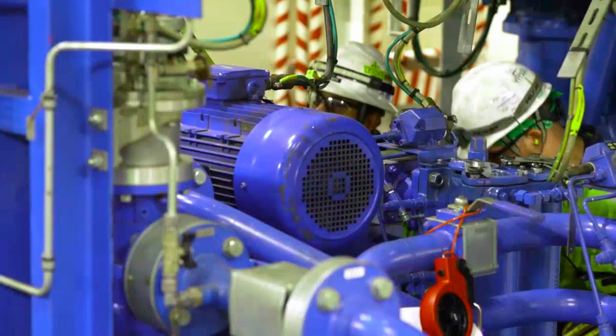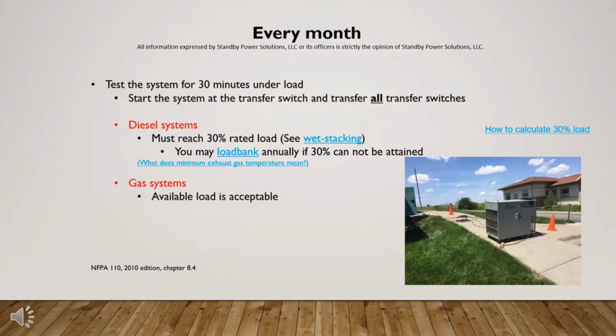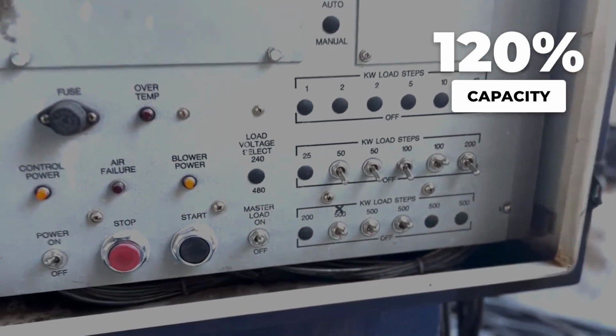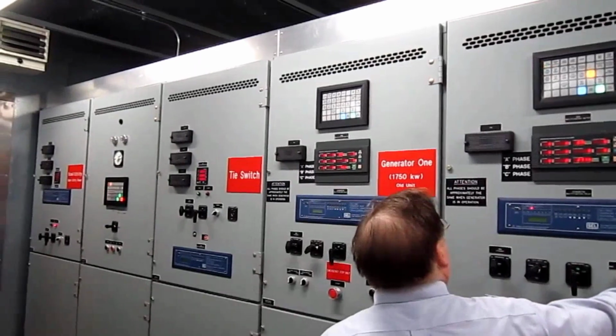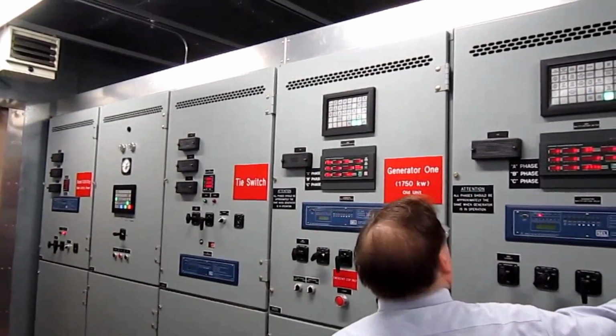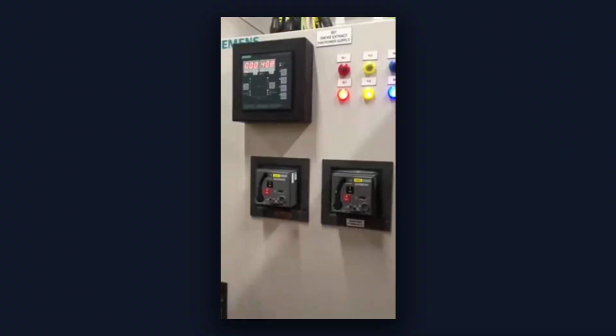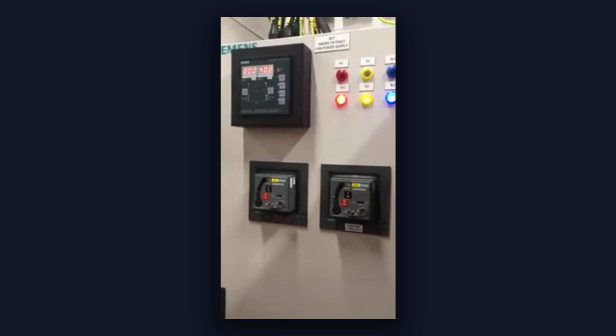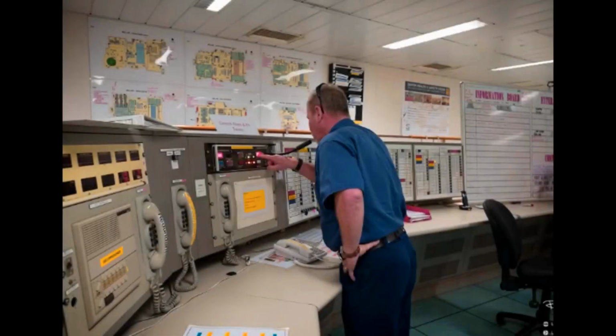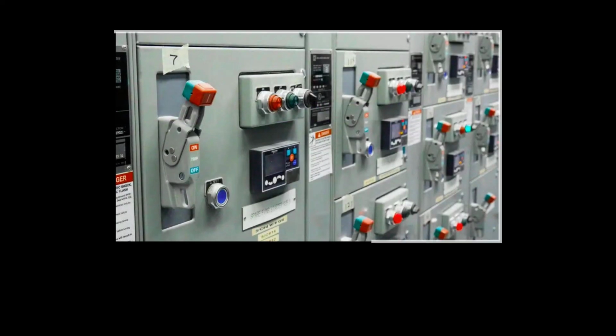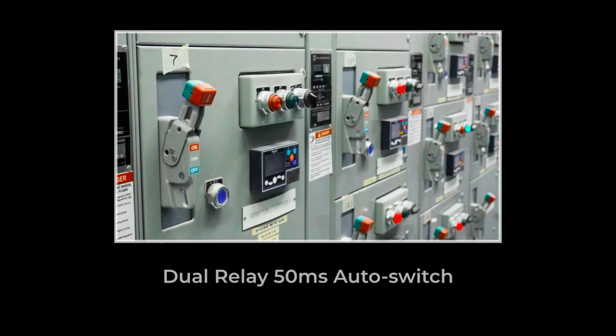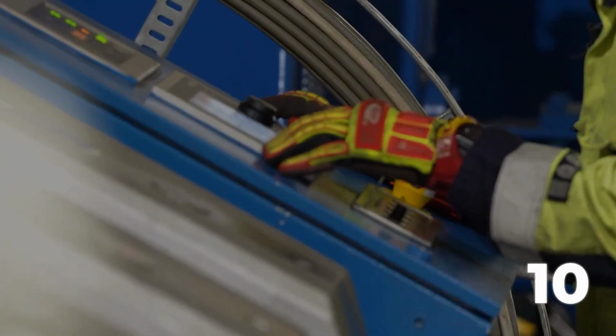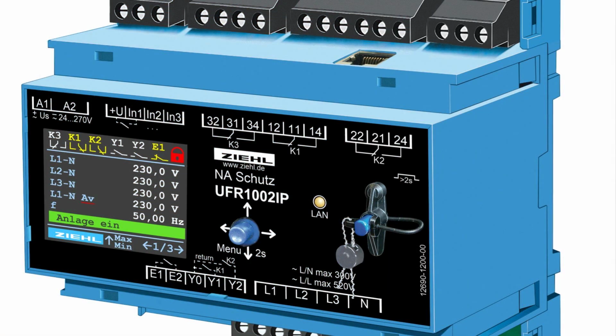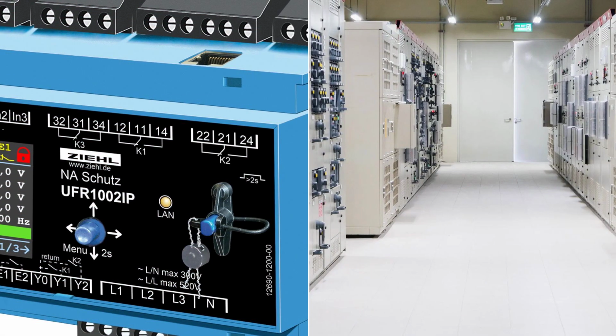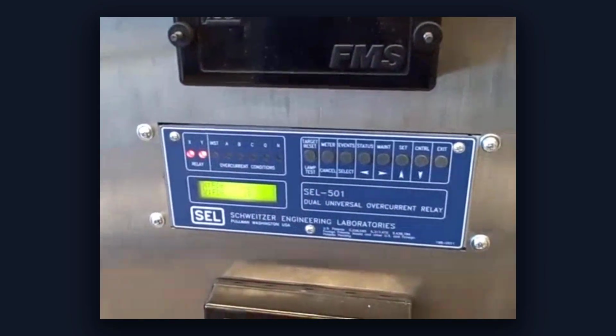The chief electrician begins each shift by checking the status of the primary and standby generators. Each is sized to handle 120% of the platform's peak demand, ensuring that if one fails, the other can carry the full load without hesitation. Automatic transfer switches monitor voltage and frequency around the clock. If the primary generator drops out of range, the transfer logic, built with both a microprocessor and a hardware relay, initiates a handover to the standby unit in less than 10 seconds. This two-part fail-safe design means that even if software fails, hardware takes over.